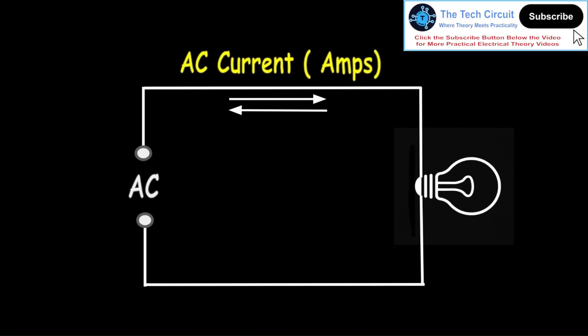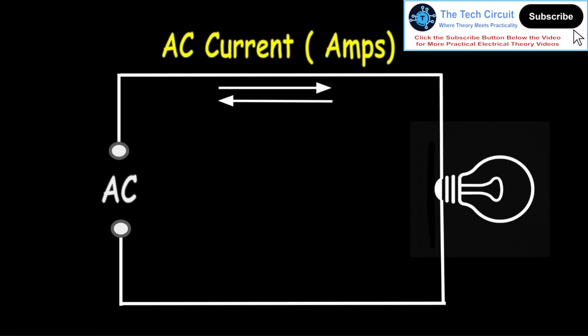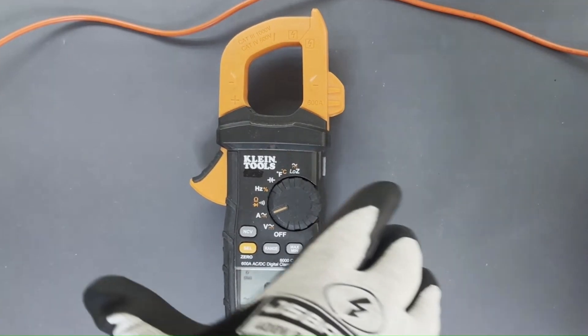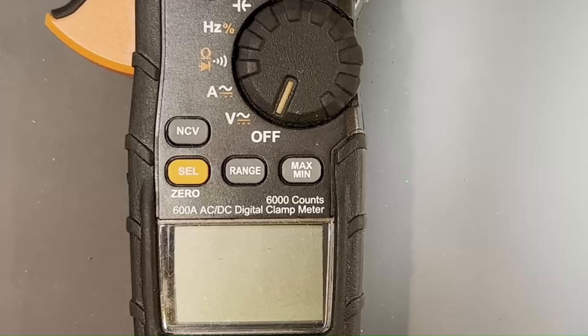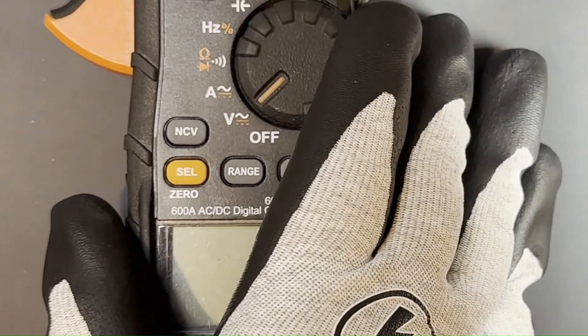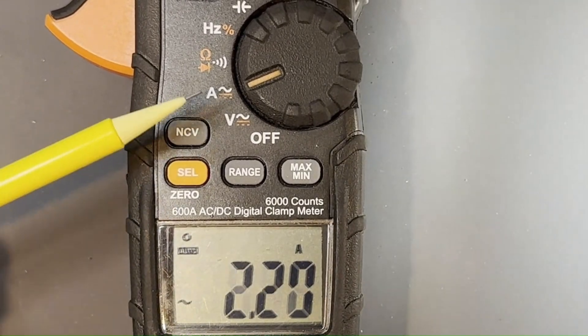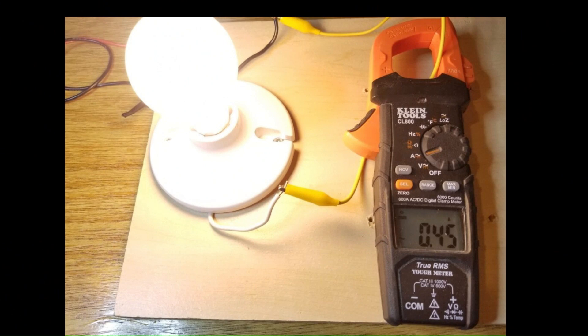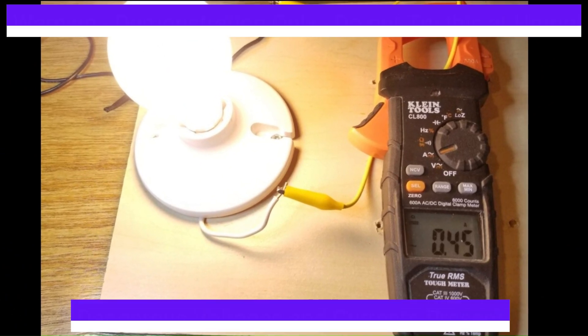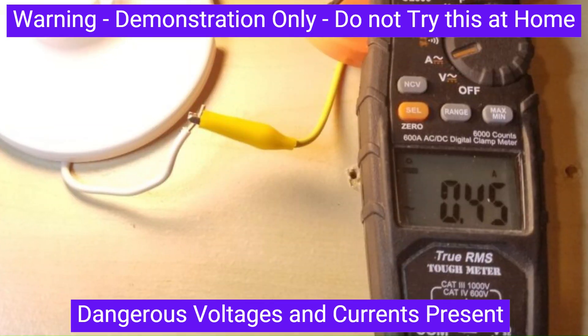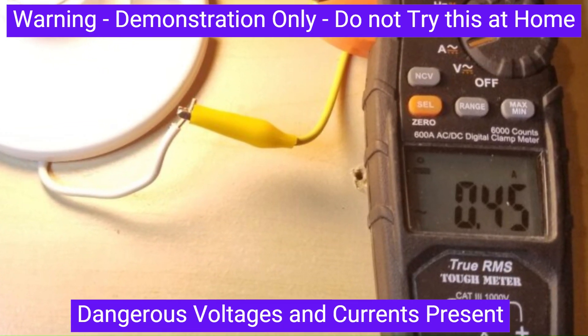Measuring AC current. The AC current function measures how much AC current is flowing through a conductor such as a wire, and is measured in amps. The Klein meter uses a non-contact clamp allowing you to place the clamp around the conductor you want to test. To measure AC current, turn the dial to the A position. The meter will default to the AC current mode. Find the single conductor you want to test. Shown here, the meter is being used to measure the current through a wire connected to a light bulb. The measured current is 0.45 amps.